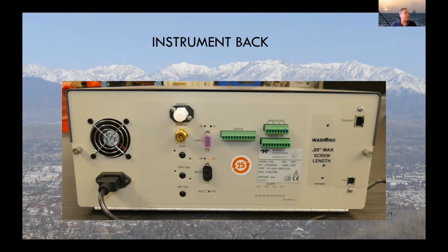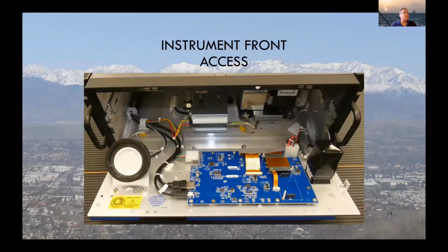The rest of these are communication ports, status ports, analog outs. Most monitoring organizations have moved to digital data acquisition, and the Ethernet port is used under those circumstances.